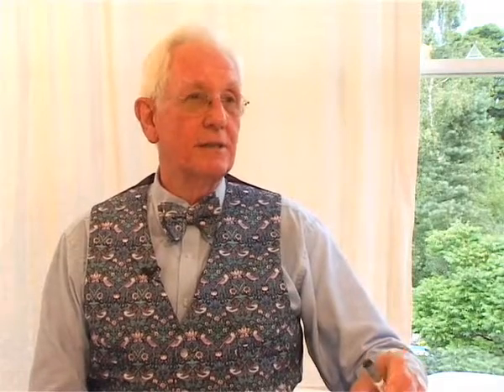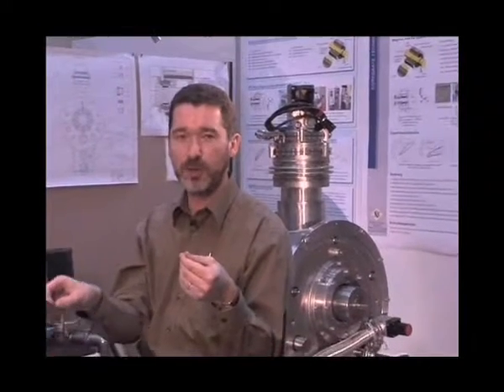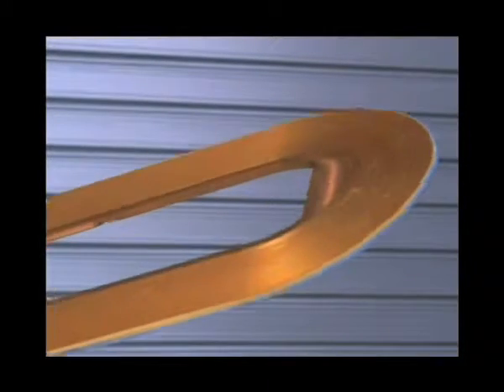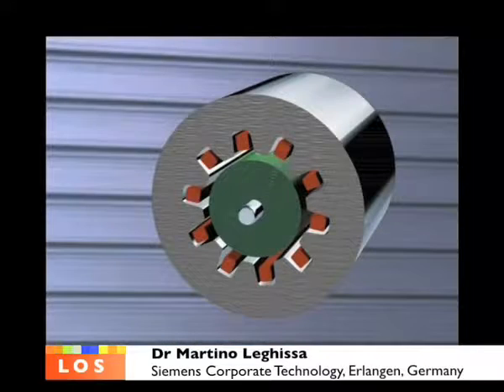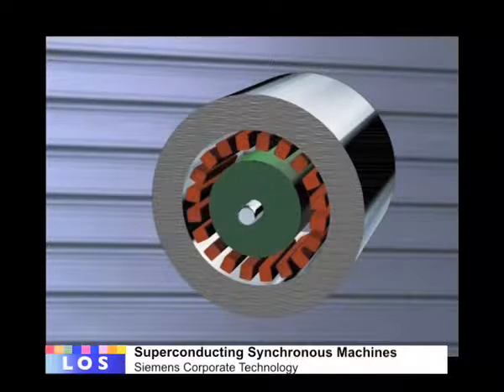with conventional non-superconducting materials. Tapes are made out of the brittle ceramic material in an elaborate high-tech process. In the superconducting state, these tapes are capable of carrying 30 times more current density than copper. This superconductor can be operated with a current of 100 amperes. For comparison, a copper conductor would need this cross-section. For use in electric machines, the tapes are processed into flat racetrack coils, which are assembled into rotor windings of the superconducting synchronous machine. This setup enables considerably stronger magnetic fields in the machine's interior. Simultaneously, it's possible to manufacture the stator with less iron, thus accommodating more power-boosting windings.